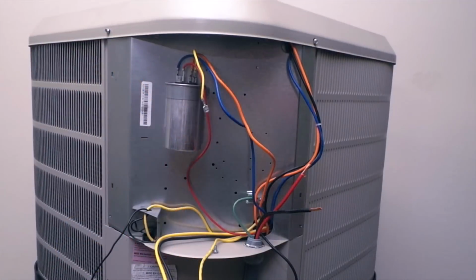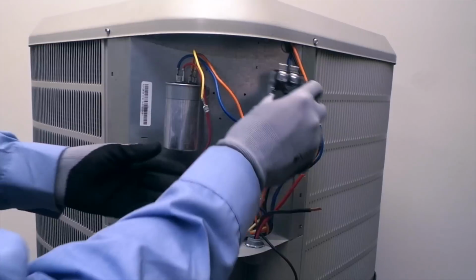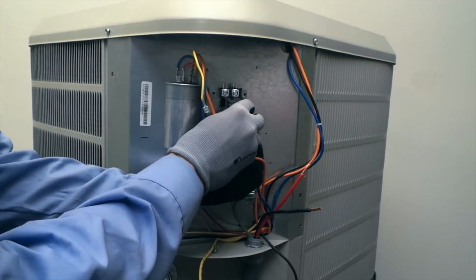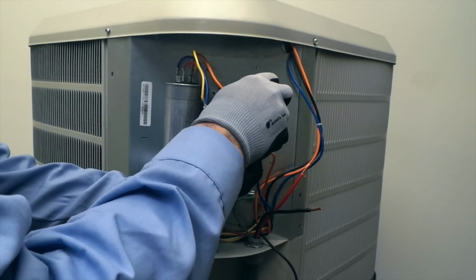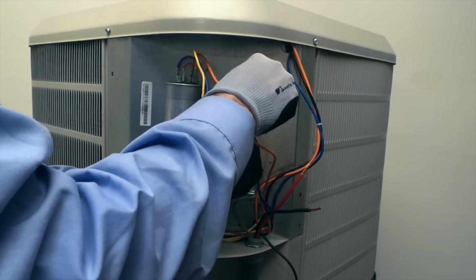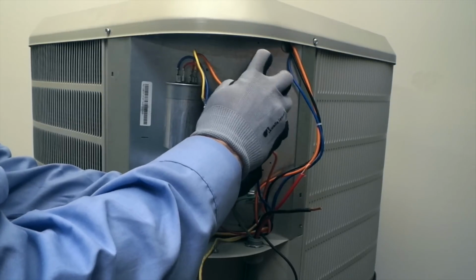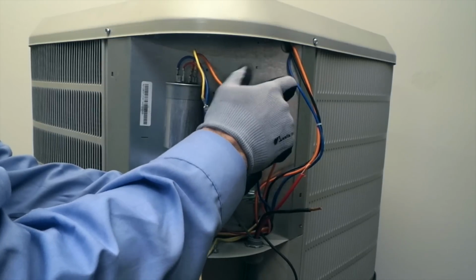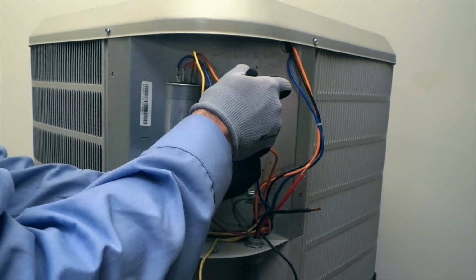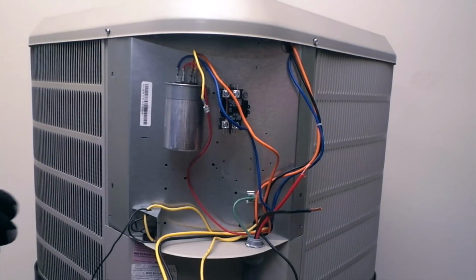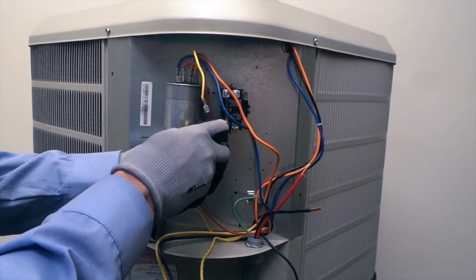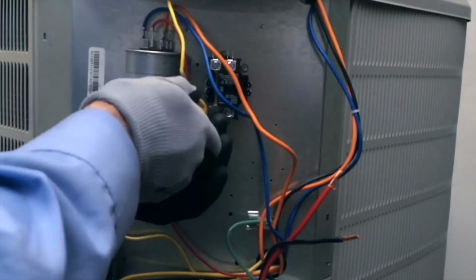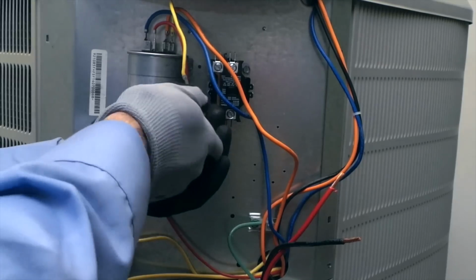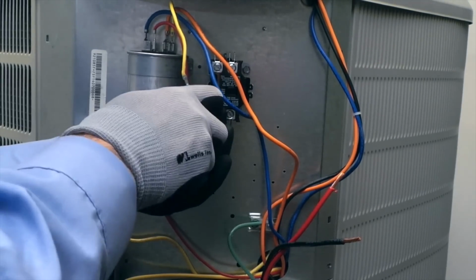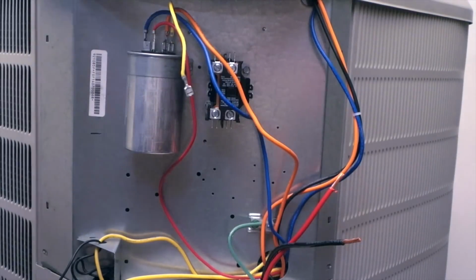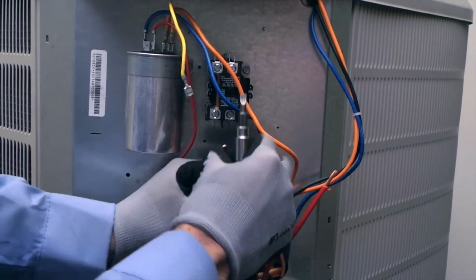Now we're ready to install our new contactor. Remember, our original contactor was a single pole contactor with the contacts on the right side of the contactor. So we want to make sure that we install our new contactor in the same position, with the contacts on the right and the shunted circuit with the bus bar on the left. Make sure that our screws are nice and tight. Interesting to note that on our new contactor, there are lugs on the bottom and also lugs on the top. So we're going to need to make some adjustments in our wiring connections to accommodate for this new configuration. Don't worry, that will come later in our video.